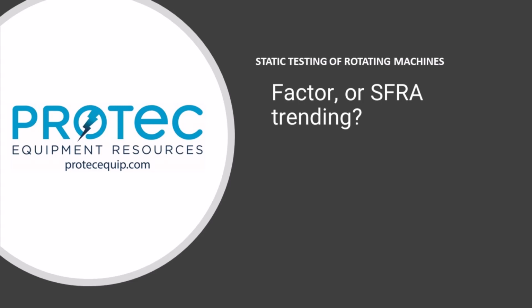But as you can see by my very long-winded answer, I really can't say which is the best. It really is what you are most concerned about, or where you want to focus. If I had to select two, I like the SFRA trending. However, I do have to take the motor out of service to do this, but it's a quick test to tell me if there's been anything mechanical that has changed inside the motor. The partial discharge can be done as an online test. So I really like this one because it lends itself to predictive maintenance, and trending partial discharges over time could give me clues as to different failure mechanisms that are causing the PD. But that's about as deep as I can get into it without going for the next 45 minutes to an hour. Michael, if you want, contact me privately and we can really go deep into this conversation.